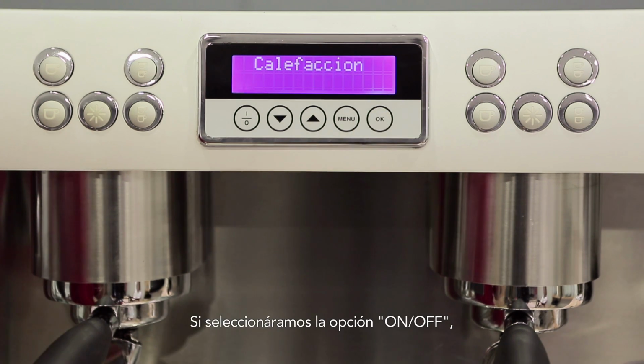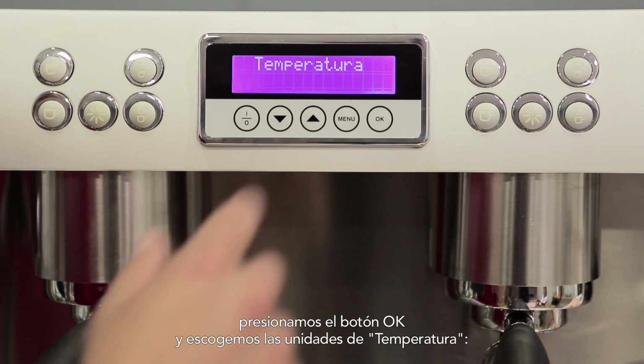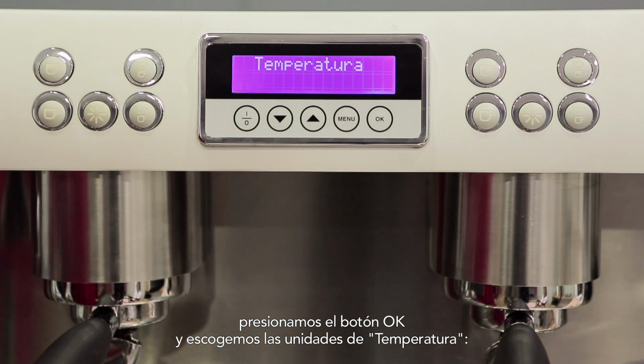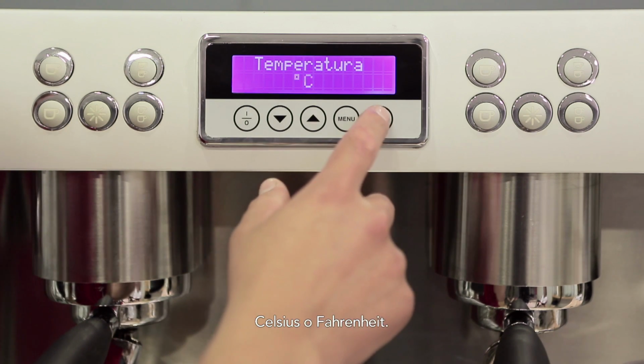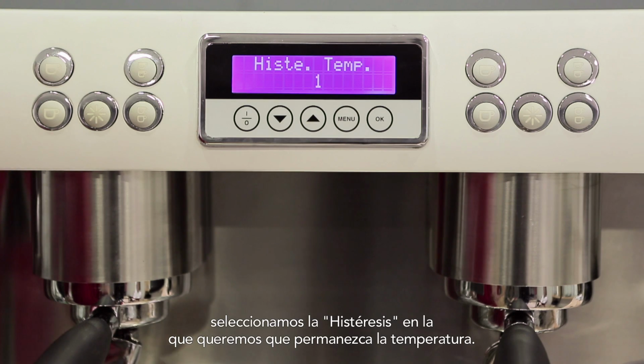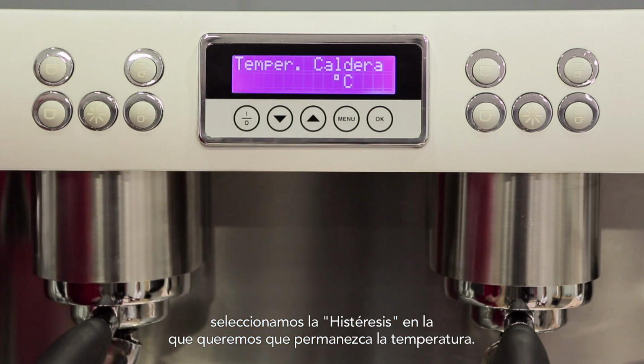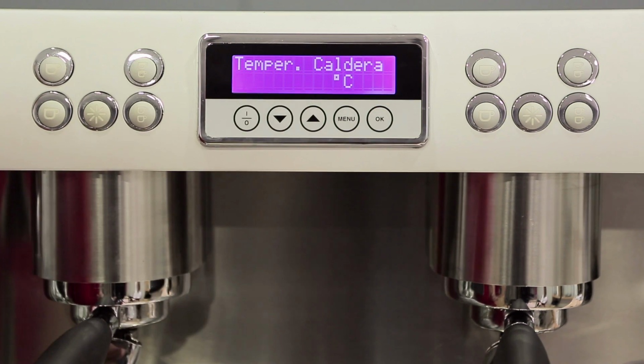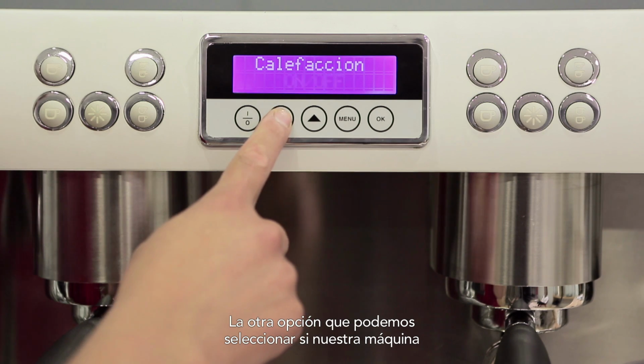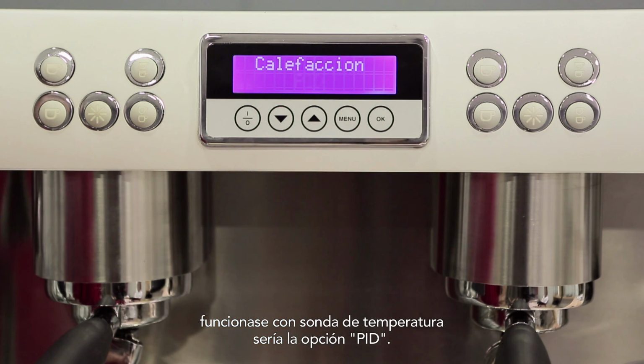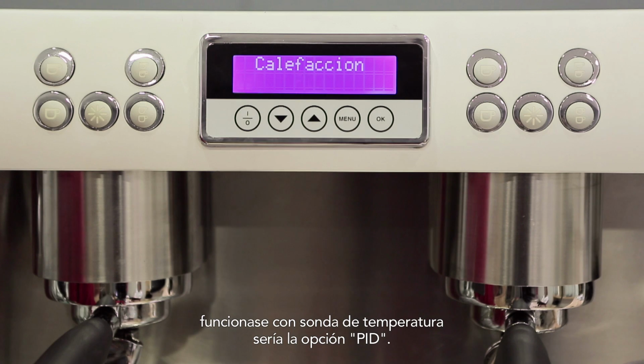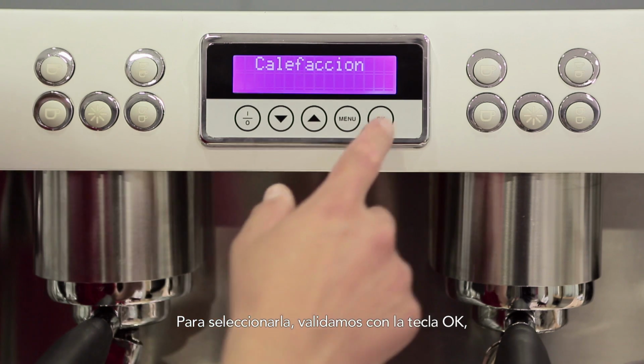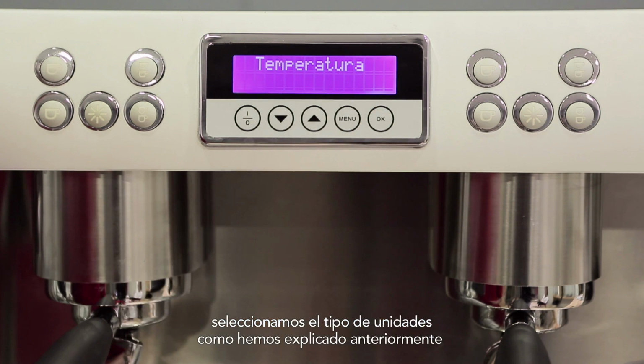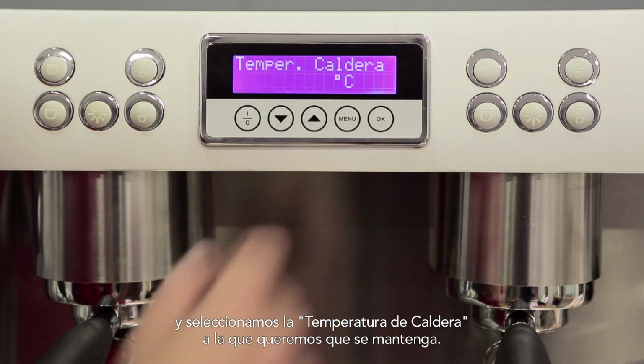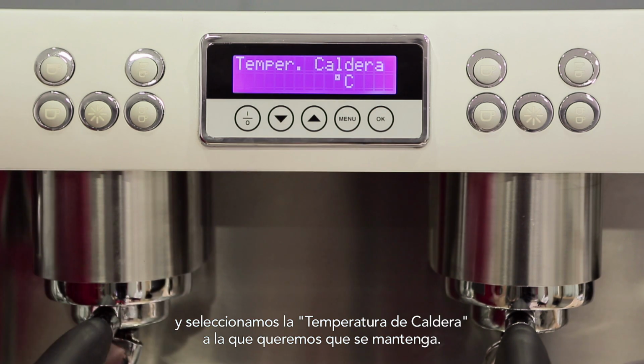If we select the option On-Off, we press the OK button and choose the temperature units, Celsius or Fahrenheit. Afterwards, we select the gap within which we want the temperature to stay. The other option that we can select if our machine works with a temperature probe is the PID option. To select this option, we confirm with the OK button. Select the temperature units, as previously explained, and select the temperature we wish the boiler to remain at.